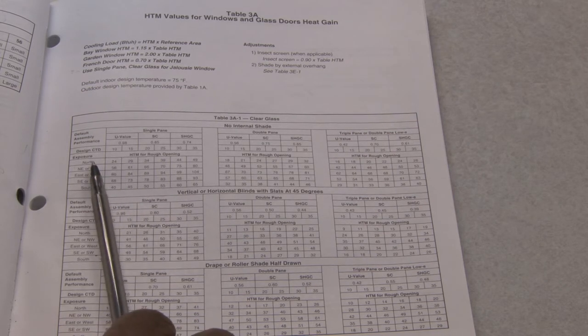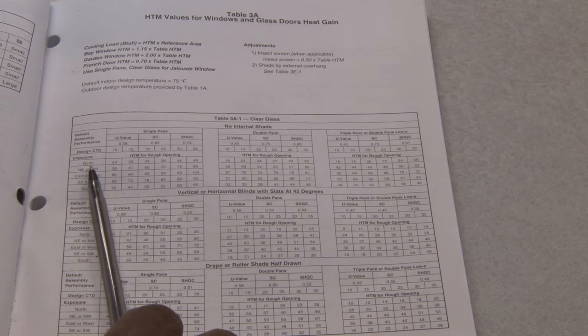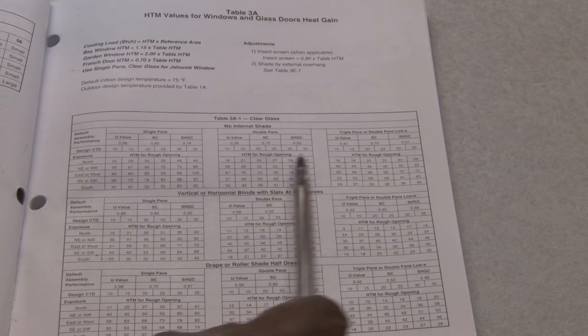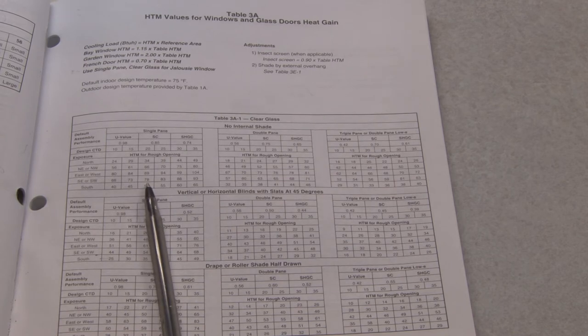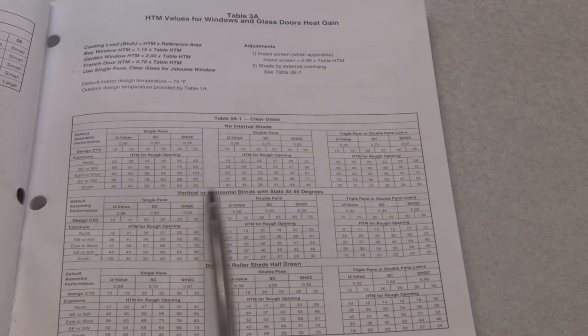But in the summertime it's going against us. It's actually adding heat we want to get rid of. So based on the orientation and direction of the window or door, if you've got glass windows in a door, that heat can transfer through and cause us to gain more heat, and we have to consider that when sizing up our air conditioning system, because we have to get rid of that type of heat.